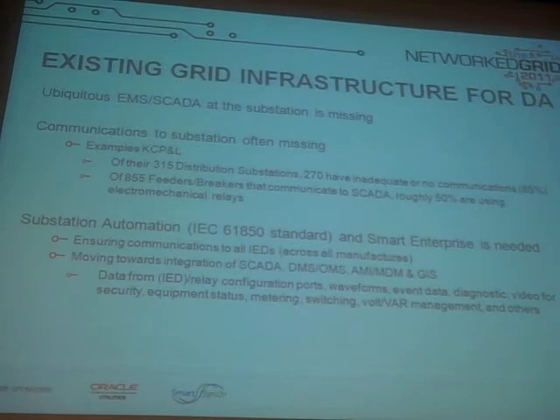Before we can get to the edge of the grid, substation automation is obviously very important. We have the 61850 standard in place so different IEDs from all kinds of manufacturers can communicate. But it's about getting more substation automation at larger substations, and this idea - we're doing a report on this right now - of the smart enterprise, where all your applications, which today are quite siloed, come together. Even at some advanced utilities, you still have separate screens for SCADA and EMS, for DMS, and outage management. So the data is beginning to be shared, but the operator is still having to look at 3 screens. It's the integration of all this data into a centralized command using real-time information from the grid that's going to take this into the next decade.